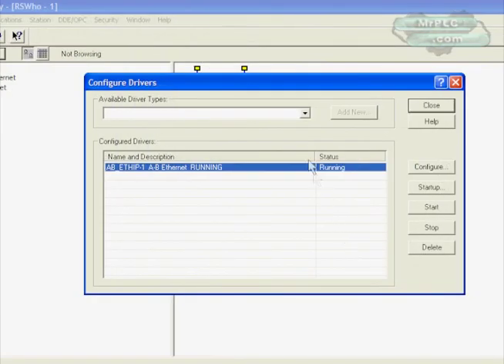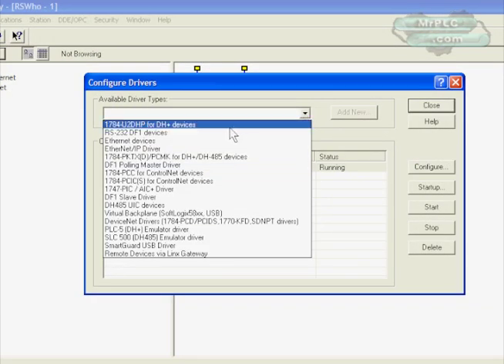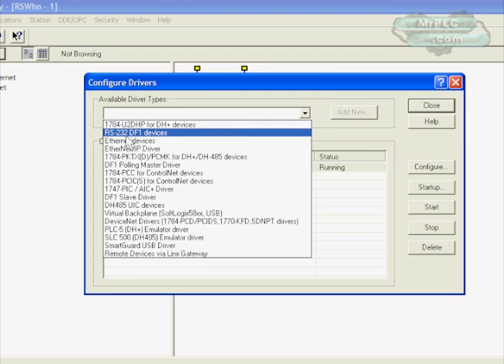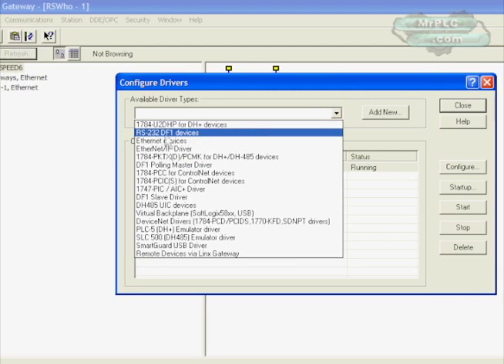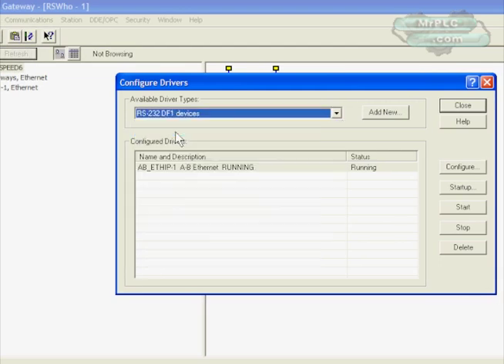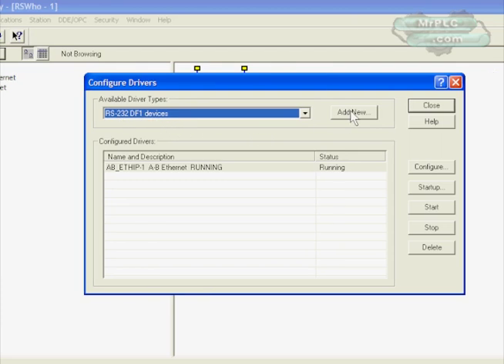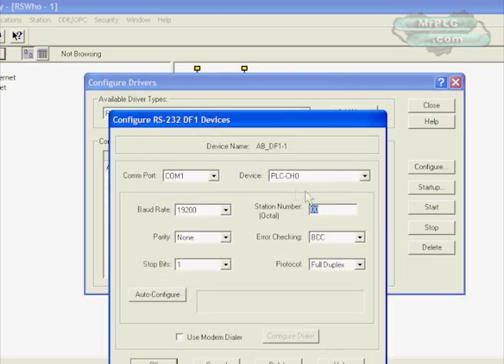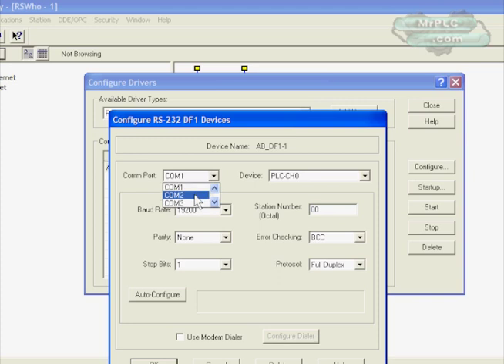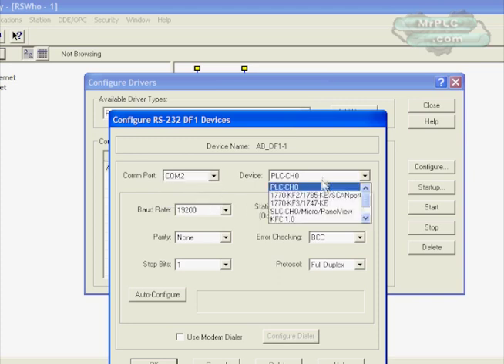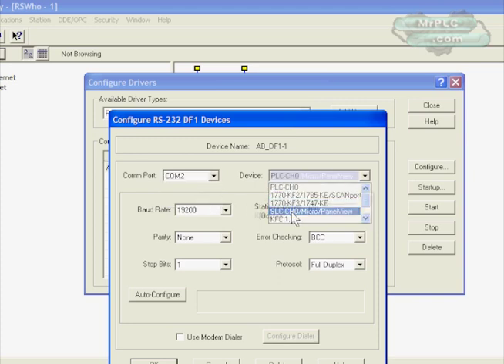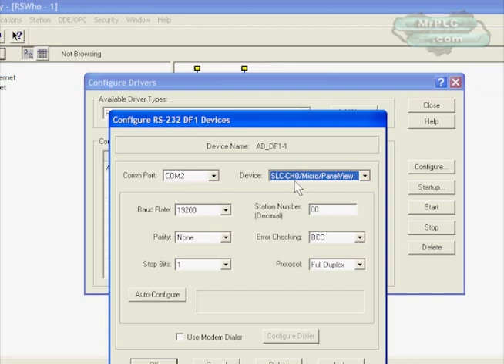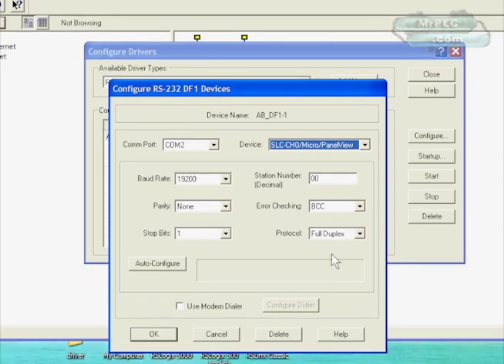The first thing we want to do is go to the Communications tab and Configure Drivers. We are connecting to a Micrologix 1000, so that uses RS 232 DF1 to communicate with. We're going to configure an RS 232 DF1 driver for RSLinx. Go ahead and click Add New. You can leave this as a default DF1.